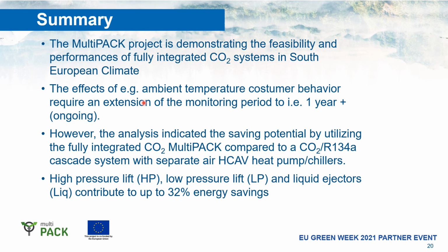So all in all, short summary, the MultiPACK project is demonstrating the feasibility and performance of fully integrated CO2 systems in Southern Europe climates, in this case for Portugal. The effects of the ambient temperature and of course the consumer behavior of the supermarkets require an extension in the monitoring period, for example, a year or a year plus. So this monitoring is still ongoing. The analysis conducted indicates a big saving potential by utilizing fully integrated CO2 multipacks compared to, for example, CO2 and R134A cascade systems with separate air handling units. What is also interesting to see is that, of course, the combination of high pressure lift, low pressure lift and liquid ejectors contributes to energy savings in the order of 32%.